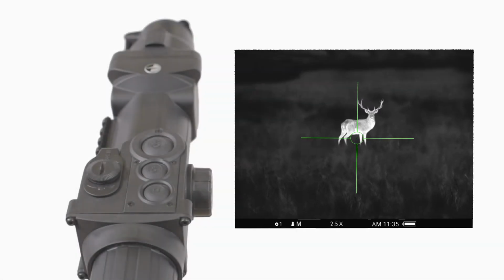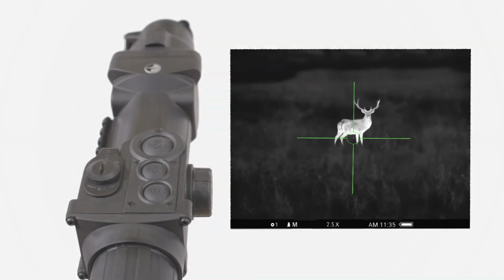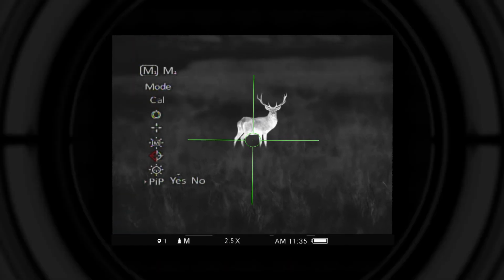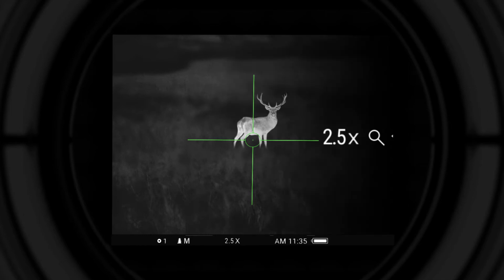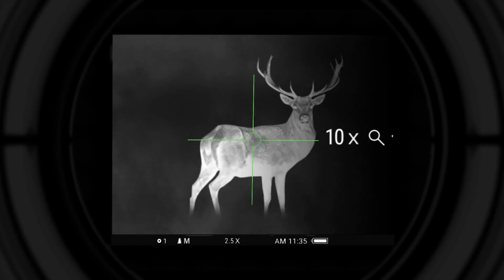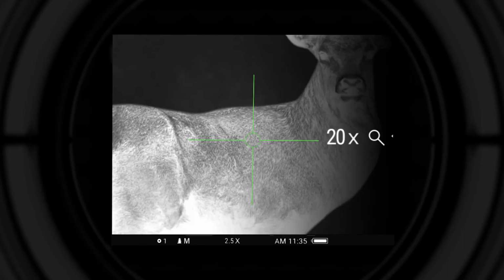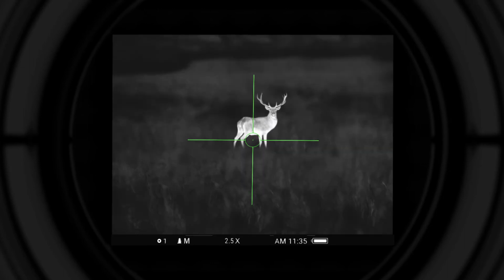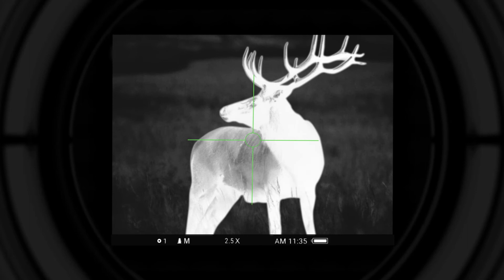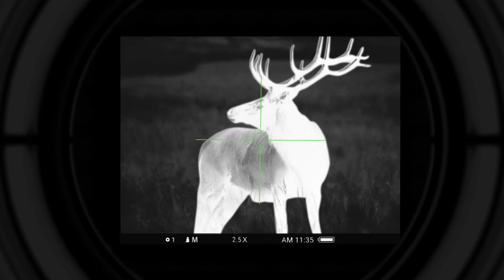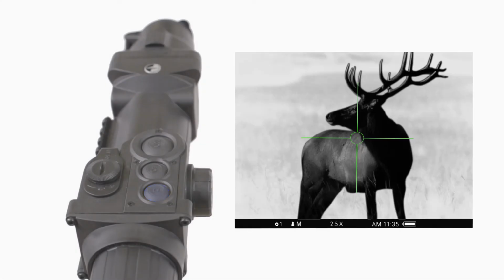A short press of the mode button activates digital zoom or picture-in-picture. Picture-in-picture can be activated or deactivated in the menu. When the picture-in-picture is activated, digital zoom is deactivated. For digital zoom, zooming is performed progressively up to the highest zoom factor, and then reverts to its lowest magnification. For picture-in-picture, the second small image with magnification appears on the screen. A long press of the mode button activates or deactivates mode inversion.